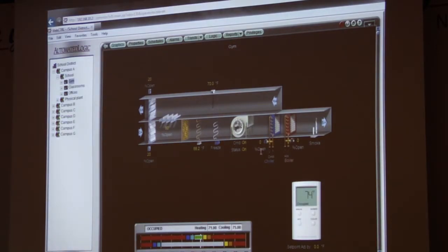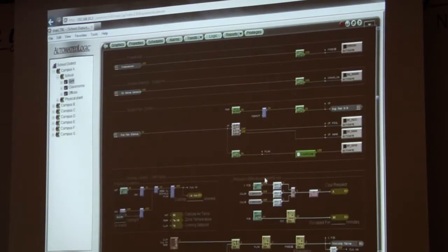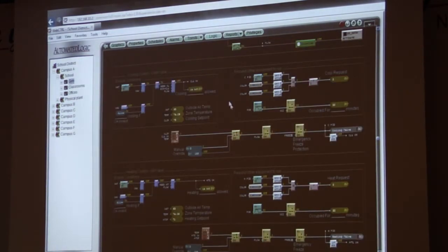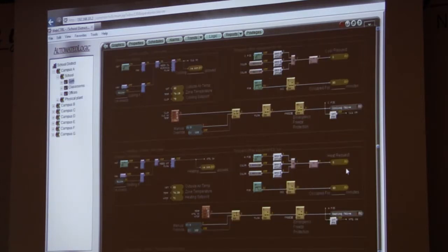My chill water valve, let's take a look at the chill water valve and the hot water valve. Let's find out, should they be open? Here's the chill water valve, here's the hot water valve. Should they be doing something? Let's take a look. They're both getting zeros, right? I could follow the wire. Look, 0, 0, 0. See over here how the switch isn't on? We could come up here and turn it and go the other way. We can see that this microblock is saying 0. Well, we don't know what it is yet.